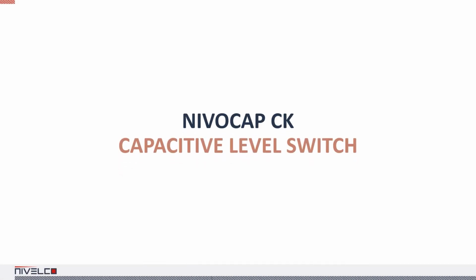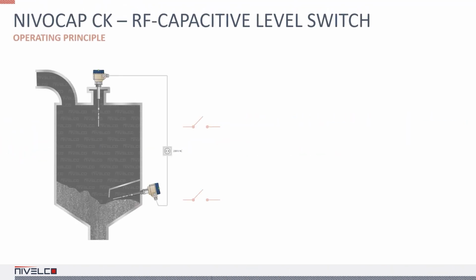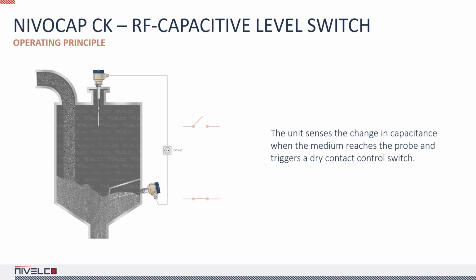Nivocap CK capacitive level switches operate as capacitance meters in the radio frequency range, which is less sensitive to material deposits than conventional capacitive devices. The Nivocap CK's electronics continuously evaluates the voltage level proportional to the capacitance difference between the two probes and the housing. The unit senses the capacitance change when the medium touches the probe and triggers a dry contact control switch. Using a reference probe enables the device to ignore large deposits on the probes, preventing false switching. The high temperature and DustEx models are suitable for harsh environments, so they are ideal for power generation applications.